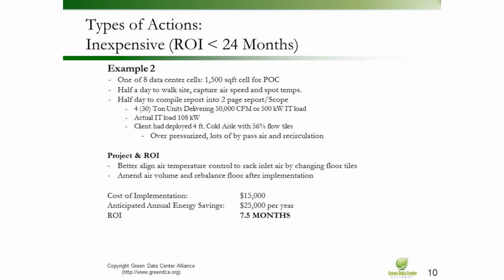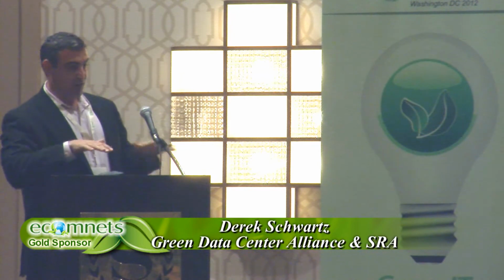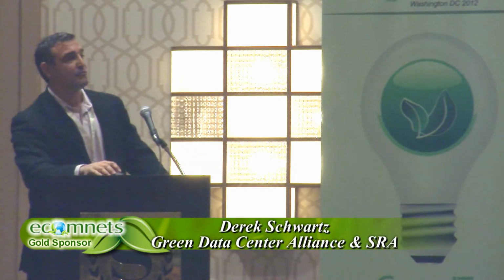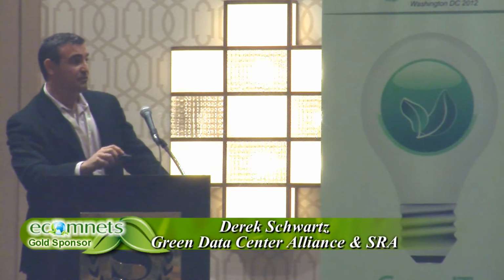So they had deployed 4-foot cold aisles with 56% airflow tiles. If you know what they look like, it just looks like an open metal grate, and they were side by side. So essentially, there was no speed to the air. So what we had suggested was there's a new type of floor tile, costs roughly the same as a regular floor tile, that has fins on the bottom that would direct the air a little bit better.